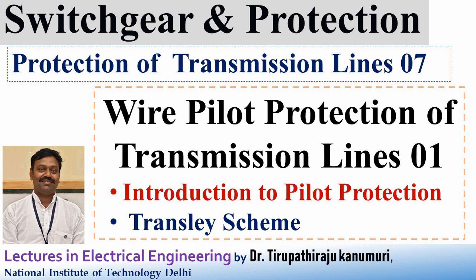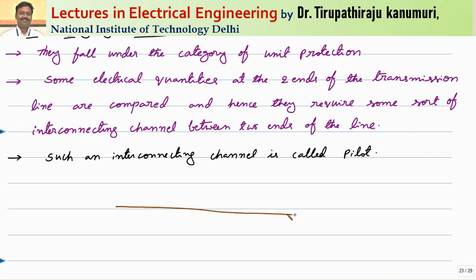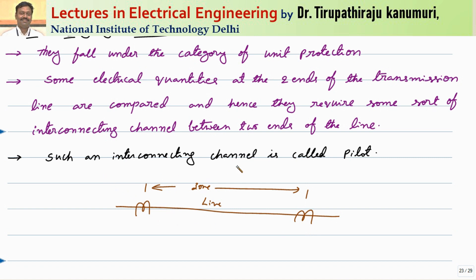Today we are going to discuss about pilot wire protection schemes of transmission lines. Pilot wire protection comes under the category of unit protection. In unit protection, CTs are connected at both ends of the transmission line. The quantities from both ends are compared and accordingly a decision is taken — whichever zone we want to protect, CTs are placed on both ends of that zone. We can either compare currents on the secondary side or compare voltages. The interconnecting channel that links these two quantities is called the pilot, which is why it is called pilot protection.